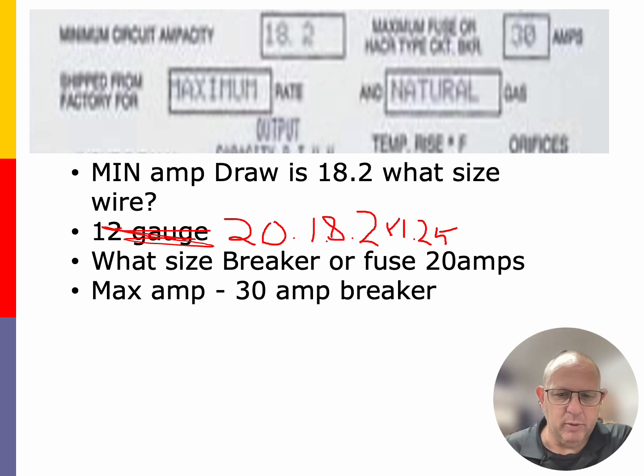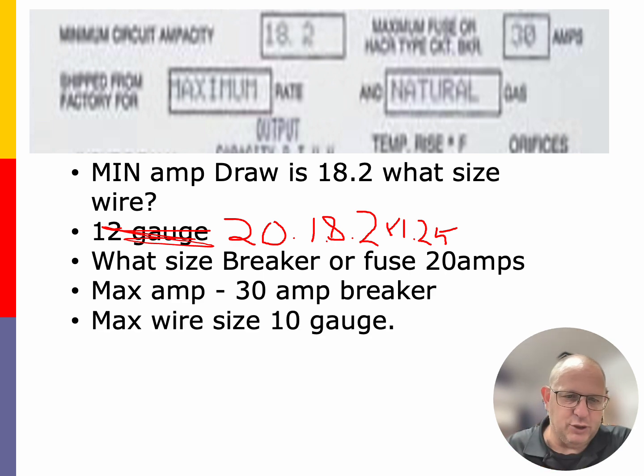What size wire? Going back to our other slide, we can see the size wire that we want to use for this is a 10 gauge wire. That 10 gauge wire is good for 30 amps. I do not want to put a breaker in that's larger than 30 amps on this. One, the tag told me not to. The second thing is, if I ran a 10 gauge wire and I put a breaker in that was over 30 amps, then that wire has the capability of burning up.